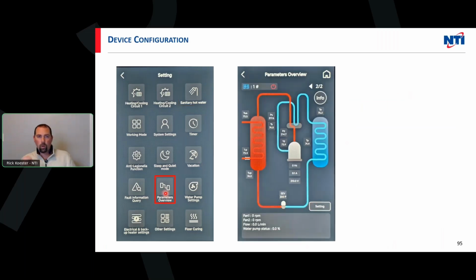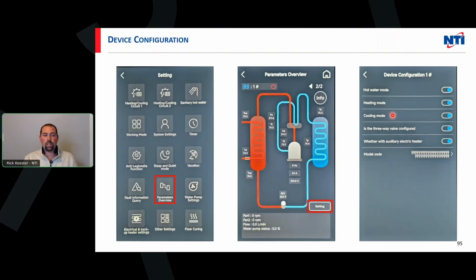You saw this before going through the ambient temperature screen. When you click on the ambient temperature on the home screen, it'll get us into these parameters overview. If I go into parameters overview here in the settings menu and drop down in the refrigeration view to setting, this will give me the opportunity to set the machine's exact configuration. Again, this will be more important as we get into cascades further on, where if I have multiple outdoor units, the working mode is going to tell me what the entire system does. The device configuration down here is going to tell me what each individual heat pump does. So if I have certain heat pumps that I'm going to dedicate to the heating, and then I need all of them to do DHW, I have the ability to do that. The same thing with cooling as well. So that'll be more in the future.